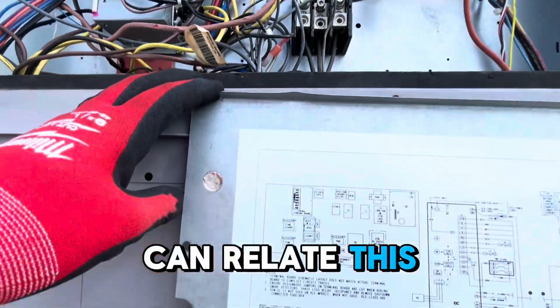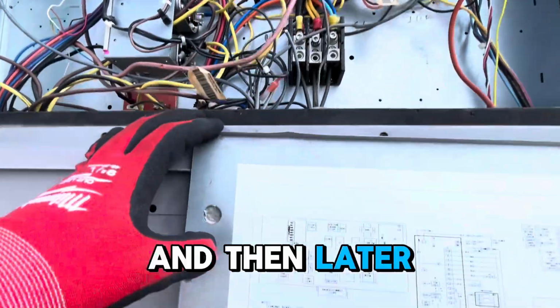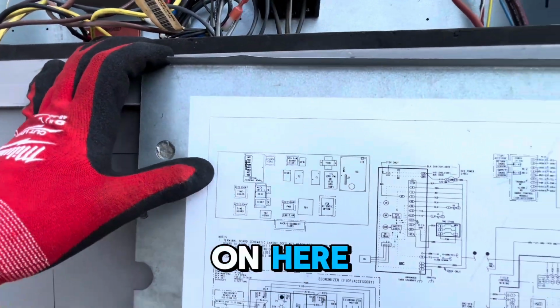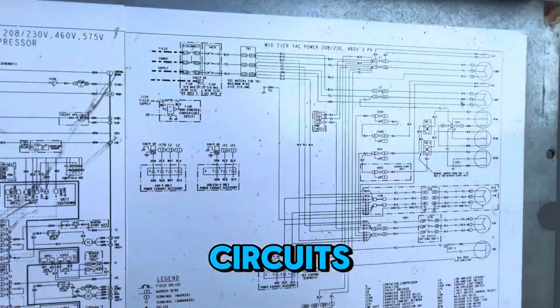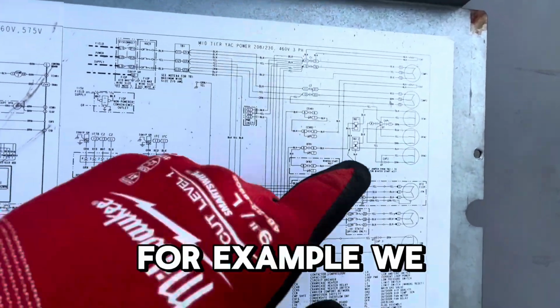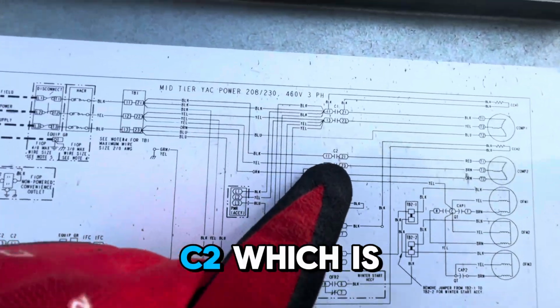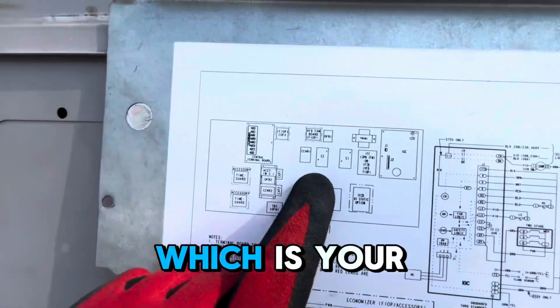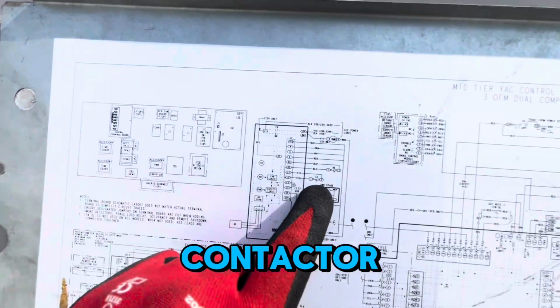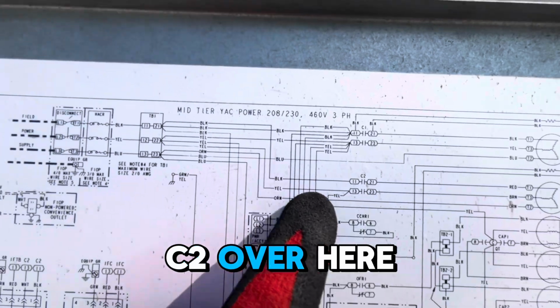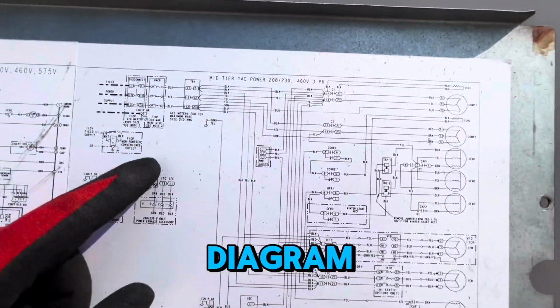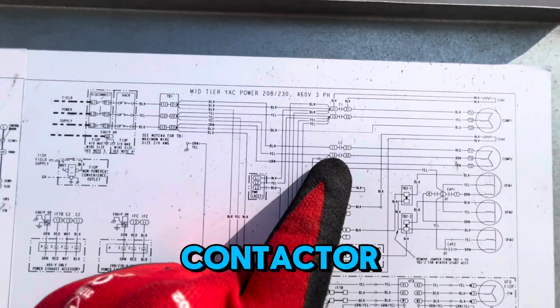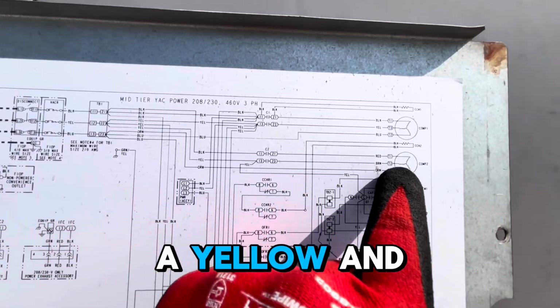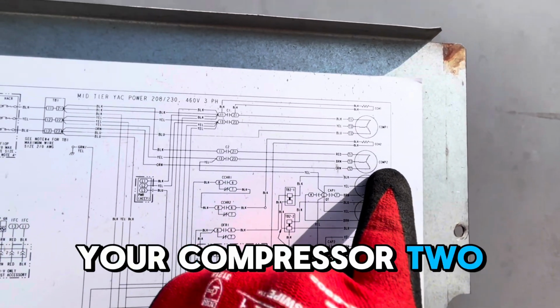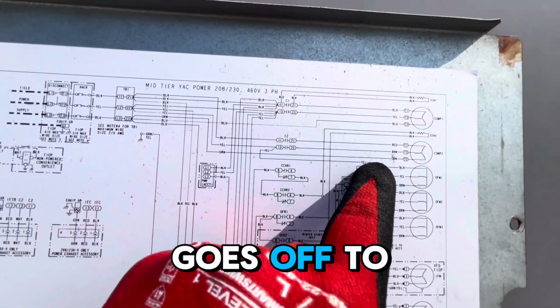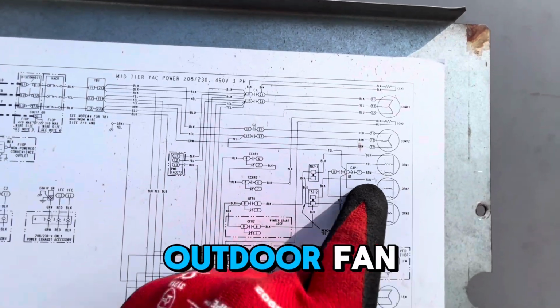So you can relate this to that, and then later you can cross-reference the words on here to your other circuits. For example, we looked at the C2, which is here, which is your contactor. So you're going C2 over here, that's your line diagram. So you see C2, that's your contactor. So you have a black and a yellow, and you see that goes to your compressor too. And then this goes off to the yellow and goes here also to the outdoor fan.